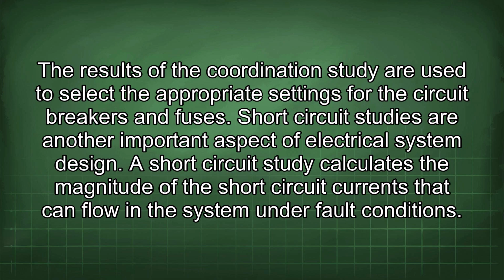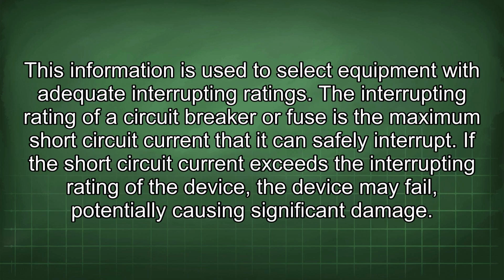Short-circuit studies are another important aspect of electrical system design. A short-circuit study calculates the magnitude of the short-circuit currents that can flow in the system under fault conditions. This information is used to select equipment with adequate interrupting ratings. The interrupting rating of a circuit breaker or fuse is the maximum short-circuit current that it can safely interrupt. If the short-circuit current exceeds the interrupting rating, the device may fail, potentially causing significant damage.